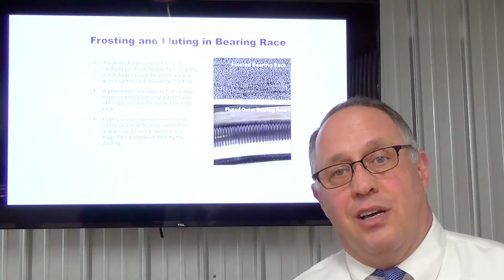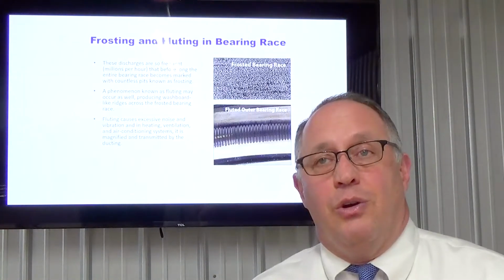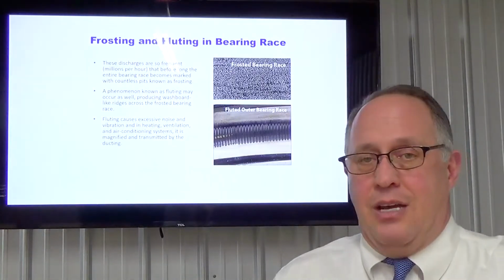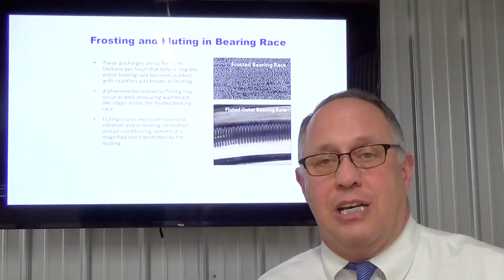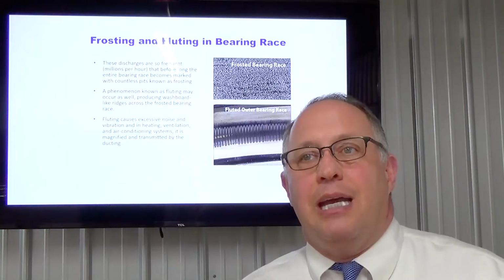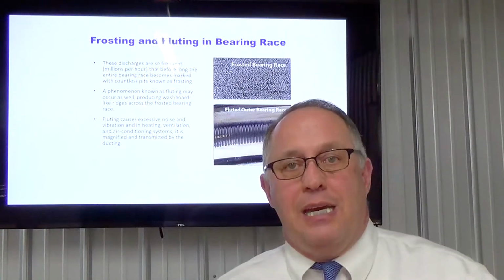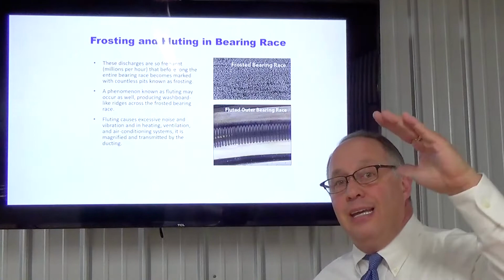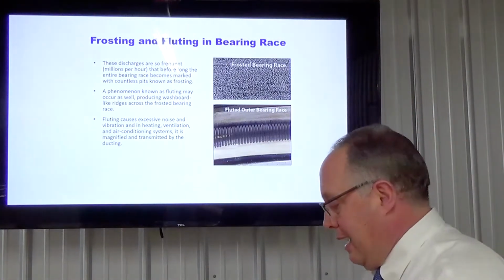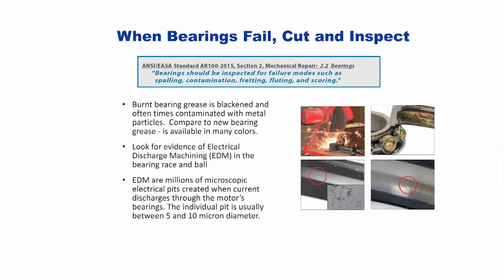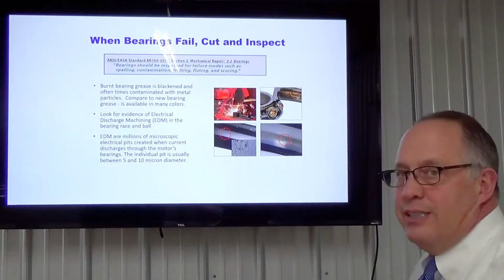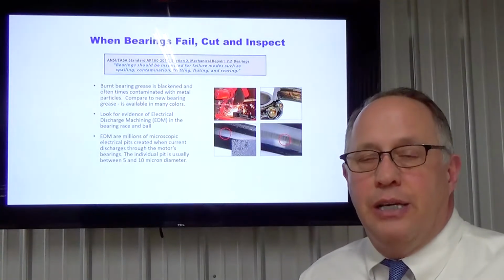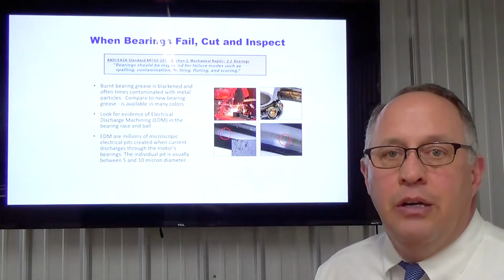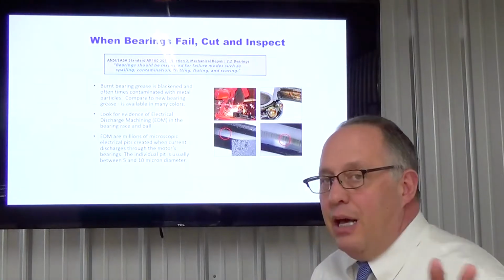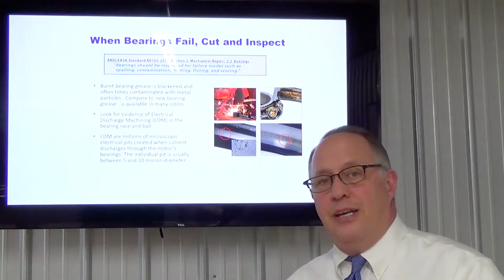You don't know if it's caused by the motor, the drive, the fan, whatever. You just hear that noise, and as you get closer, you can determine it's happening in the motor, and if you vary the speed, you determine that it is louder and more intense at higher speeds. When bearings fail, we can cut and inspect, and this is how we have done it ourselves, as well as seen the results of other field tests. I'm not saying that you would have to do this. I'm just saying this is a result.